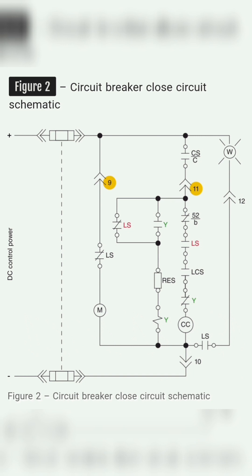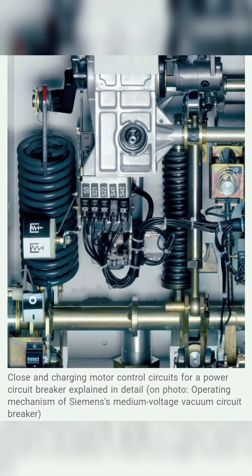Figure 2 shows the typical close and charging motor control circuit for a power circuit breaker. The function of the charging motor M is to compress the main closing spring, which is the mechanical stored energy mechanism. The energy required to trip or open the circuit breaker is provided by the tripping spring, while the energy required to close the circuit breaker is supplied by the closing spring. When the main closing spring has been fully charged and the stored energy mechanism is prepared for a closing operation, the motor cutoff switch LS creates an electrical break in the control circuit supplying the charging motor M.